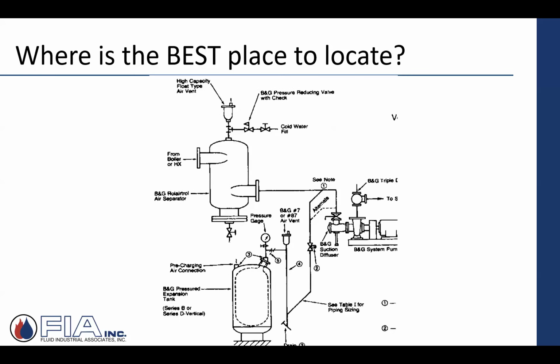Ideal location is usually as close to your expansion tank, your diaphragm, or in this case, bladder. It doesn't have to be right on it, but in this case here, it's right close to my air separation, my cold water line that's coming in with my fill valve. So it's all within very close proximity of each other. That's a pretty good location. Because the whole thing is, I want that fill valve to only respond to one thing. What's truly happening to the system's fill pressure? Not pressure changes because the boiler came on, not pressure changes because a pump turned on and either dropped pressure or added pressure. I truly want it to just respond to the actual system conditions.